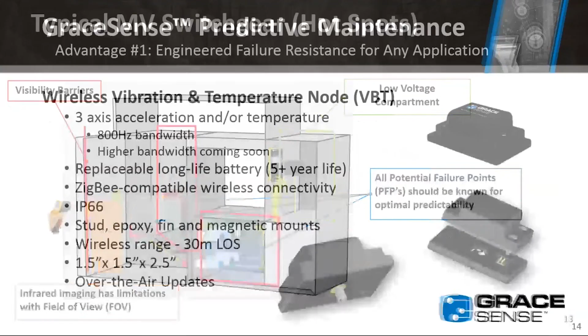Moving on from the hotspot monitor, we'll talk about our vibration and temperature node. It has a triaxial accelerometer, with 800 hertz bandwidth on our current option, but we're releasing a higher bandwidth option in the fall, 4600 hertz in the X and Y and 2200 in the Z direction. A big thing here is long battery life, so we offer 3 to 5 years at 1 hour capture settings. The device sits out there, wakes up once an hour, grabs several seconds worth of high rate data, processes that down, and sends it off to our cloud gate or control gate.